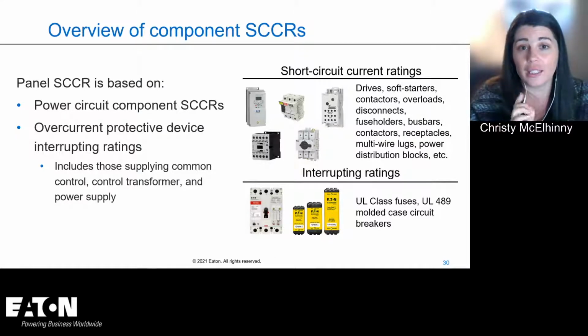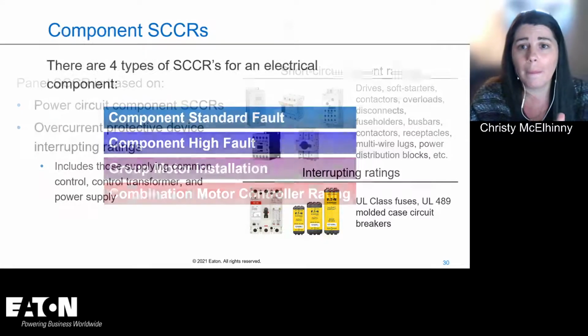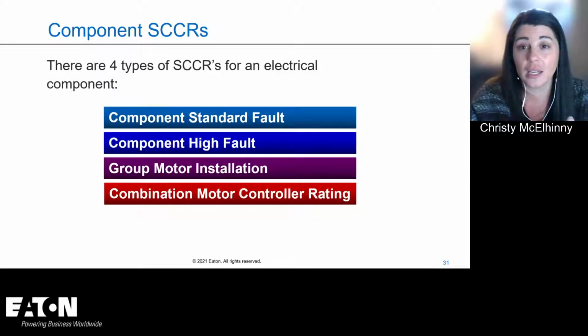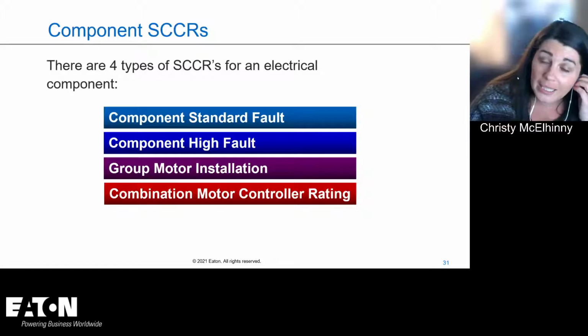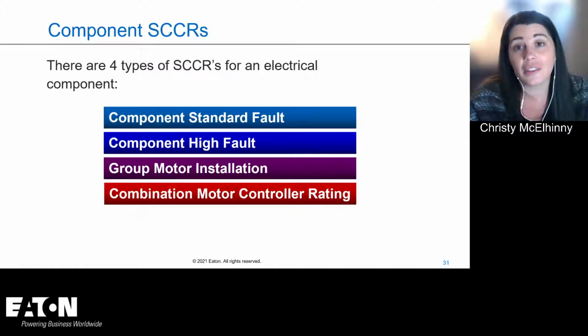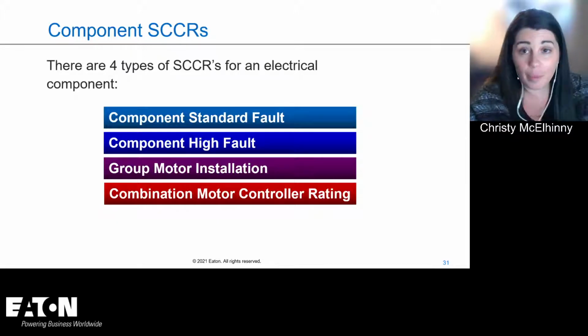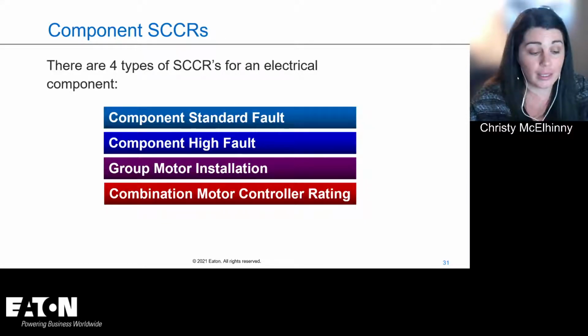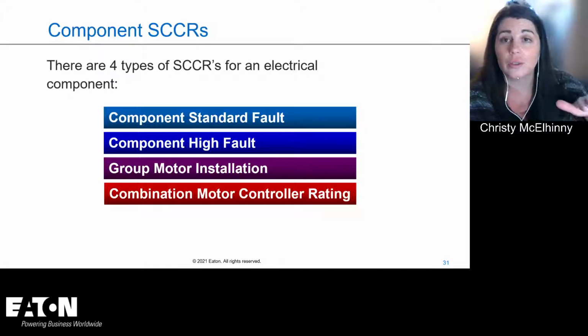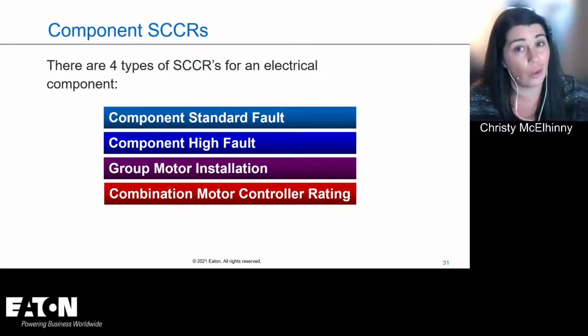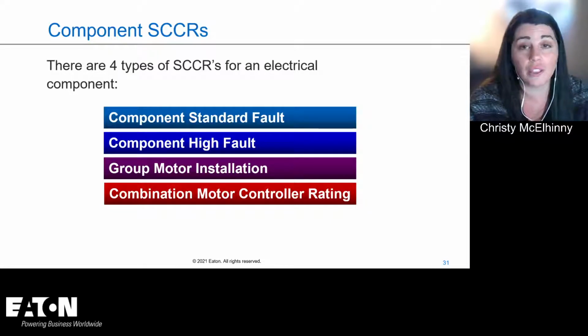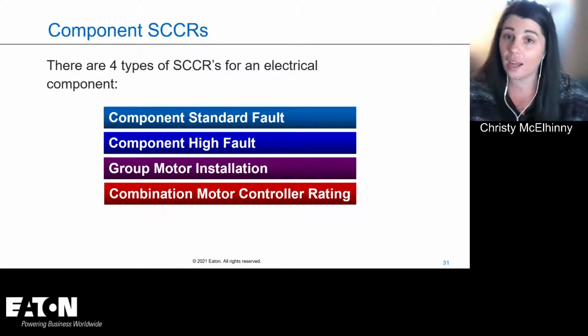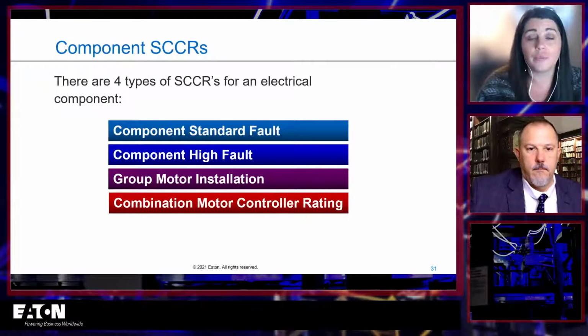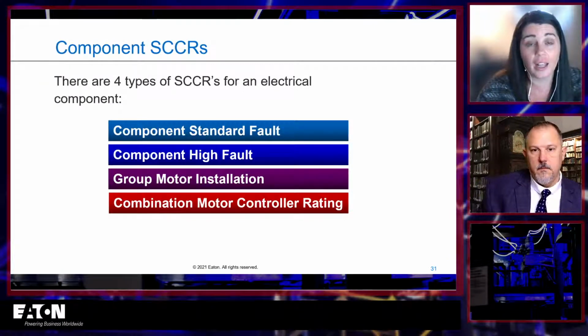So if you go to the next slide, there are 4 main types of short circuit current ratings that something could have. The first is going to be a standard fault rating. This is literally like the default rating, the minimum rating. If you're going to have a UL listed product, it must meet at its basic level a certain amount. Now, these standard fault levels are typically pretty low. So when you think of a terminal block only being 10 kA, well, that's its standard fault. There might be another way to get it higher, but by itself, standalone, it's going to be that low rating of 10 kA.